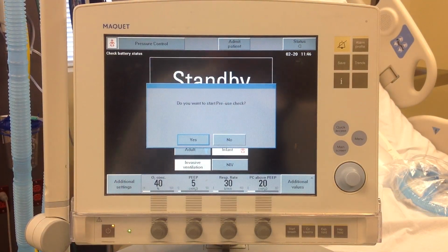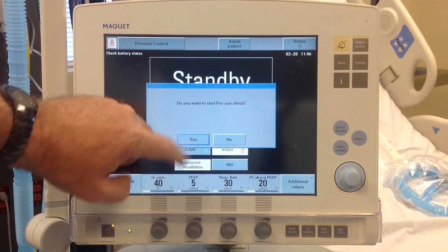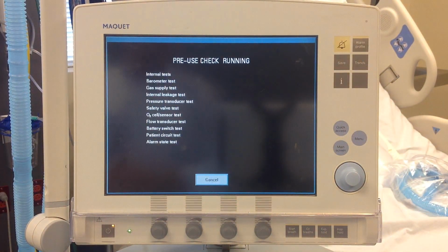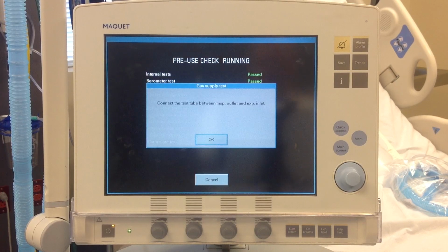Now, what this is asking, if you can see, do you want to start pre-use check? Yes, we want to do a pre-use check. It'll let the internal stuff run, and it is pretty much fully automated. It will tell you what to do. When it says connect the test tube between the inspiratory outlet and expiratory inlet, this is the hose that they're talking about.